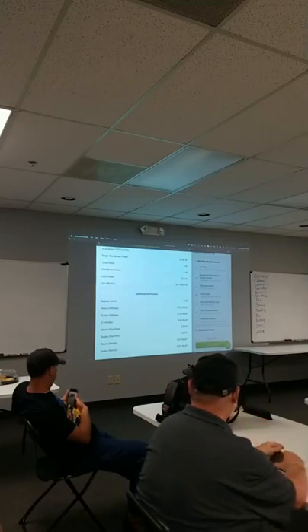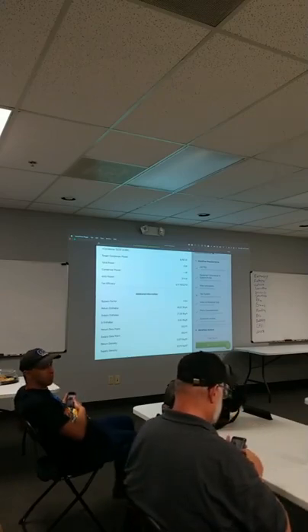You mean how are we calculating BTUs per hour? Yeah, we do it on return and supply, and then we measure the differential output. It's just calculated. So if you've got duct leakage, humidity, temperature, that's going to throw that off. Especially if you're pulling a hot return, it'll throw off the temperature split, it'll throw off everything. Yeah, absolutely. So all this is pretty important.